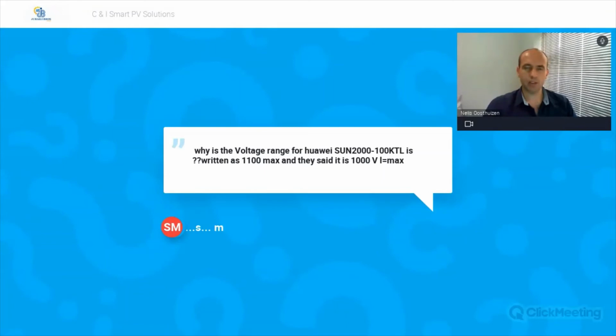So what would happen is that if your voltage exceeds 1000 volts, let's say for a duration longer than 10 seconds, then the inverter will switch off that specific string or that specific DC switch and raise it as a fault. Then after some time delay, the inverter can rescan or be rebooted. If the overvoltage was fixed, it will operate as normal. But if that overvoltage is still present, an alarm will be indicated to say that you should please have a look at your site. You've got more than 1100 volt as a maximum operating range. So please note, the operating range for the MPPT is 200 to 1000. The 1100 volts max is just the maximum that it can withstand, but it's not for continuous operation.